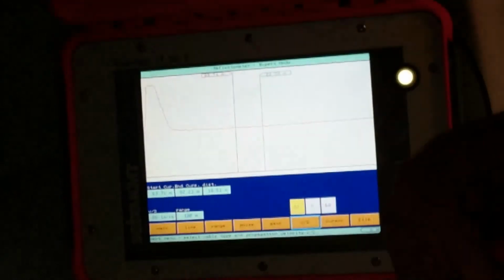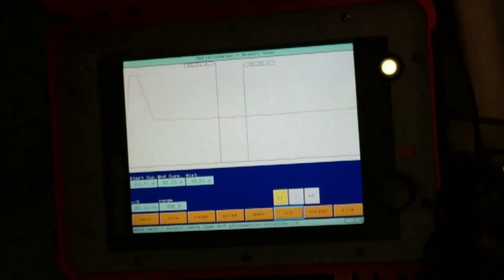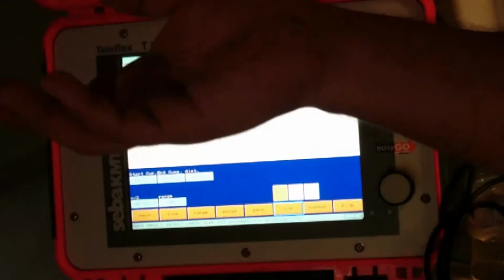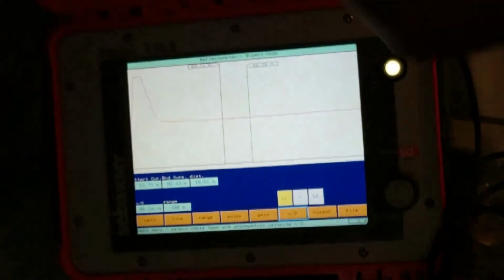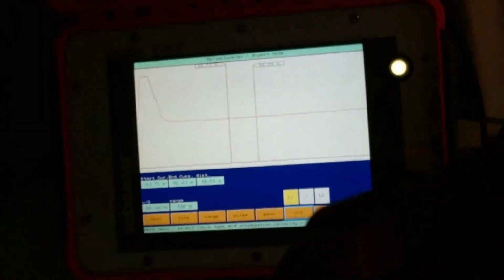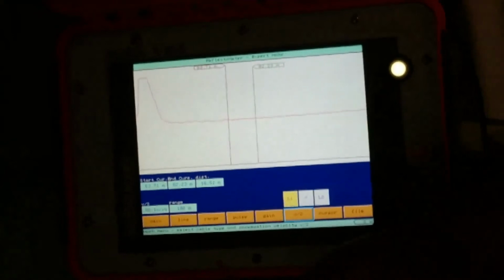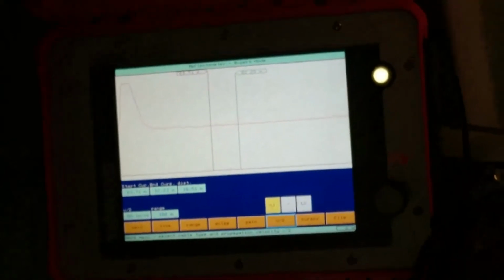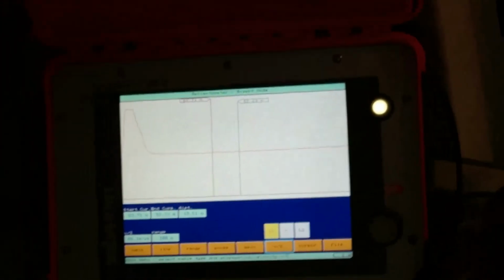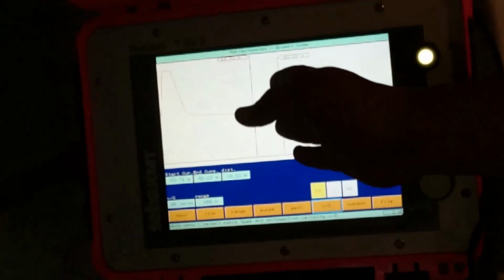So this is how you do a teleflex TDR test. You have short or open - normally we're looking for the short, not open. Sometimes the cable gets fully cut, so you also look for an open. Say I have a 1 kilometer cable, and when I test it I only get 500 meters - that means it's open, totally cut somewhere in the middle.